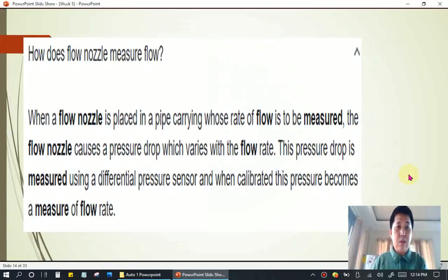Next, how does a flow meter measure flow? When a flow meter is placed in the pipe carrying the fluid whose rate of flow is to be measured, it causes a pressure drop, which varies with the flow rate. The pressure drop is measured using a differential pressure sensor, and when calibrated, this pressure becomes a measure of flow rate.